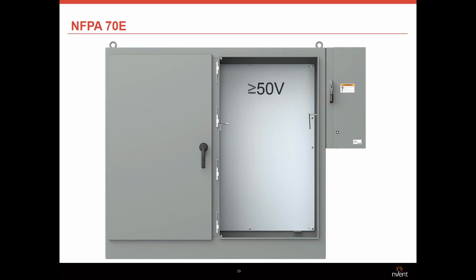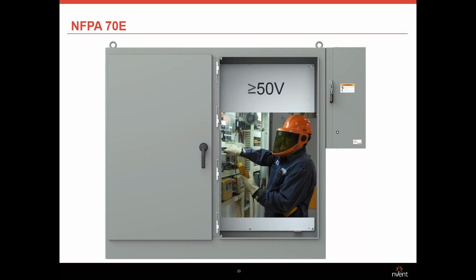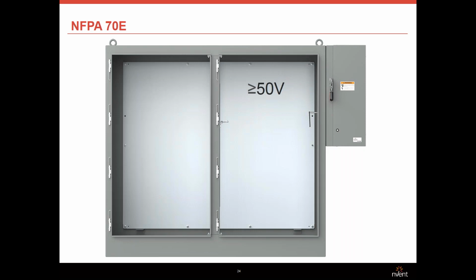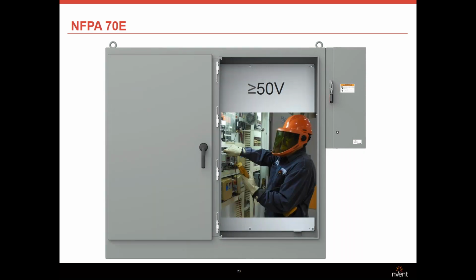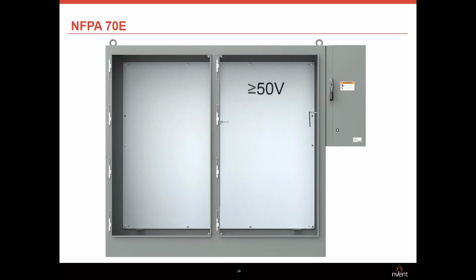With the sequester enclosure attached to the control enclosure, the highest level of PPE will be required in the sequester enclosure itself, and the enclosure being fed by the sequester enclosure will have a lower level of PPE required, depending on whether or not the calories of the energy are significantly less than what's in the sequester. With both control enclosure doors open, the PPE required will be based on the warning label of the highest rated enclosure door that is opened.